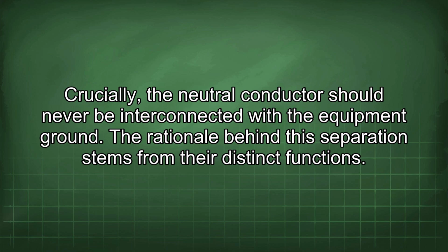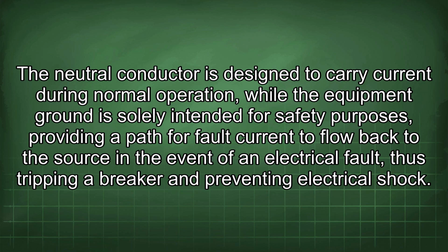The rationale behind this separation stems from their distinct functions. The neutral conductor is designed to carry current during normal operation, while the equipment ground is solely intended for safety purposes, providing a path for fault current to flow back to the source in the event of an electrical fault, thus tripping a breaker and preventing electrical shock.